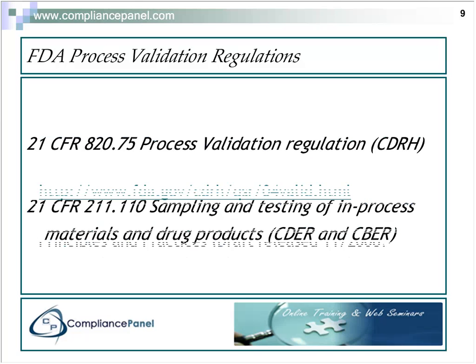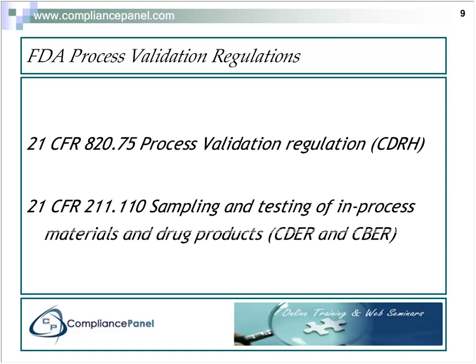Of course, in the regulation itself, 21 CFR 820, the Medical Device Quality System Regulation, does have a section on process validation. It's a very short section. It's 820.75. Certainly you need to read that, so you make sure that you do comply with each element of the required documentation you must have on hand. And again, on the CDER and CBER sides, the section there is 21 CFR 211.110, which, interestingly enough, talks about sampling and testing of in-process materials and drug products.